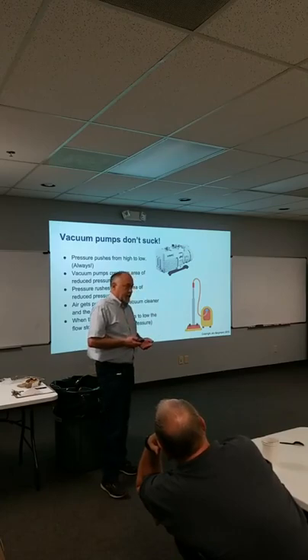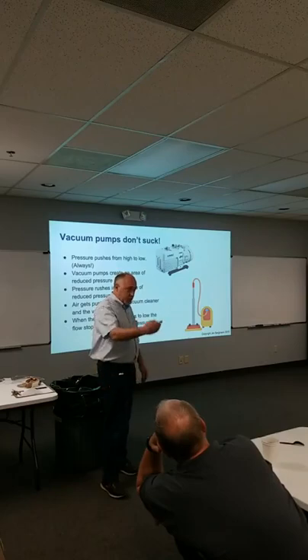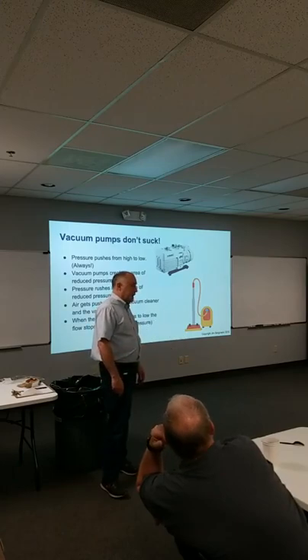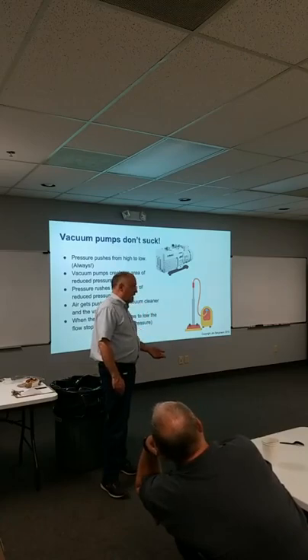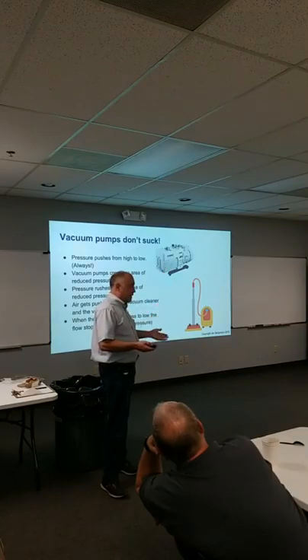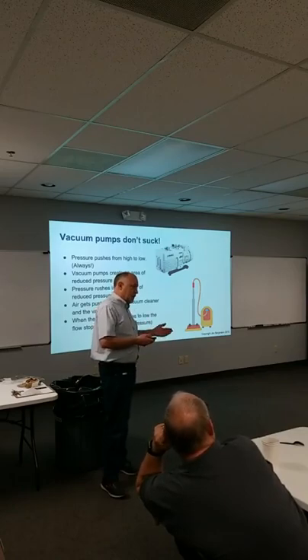When you look at an air conditioner, you're seeing the condensers getting bigger and bigger, and the condensing pressure dropping further and further. Back when we were in school, condensing temp over ambient was 30 degrees higher. You'd take your outdoor air and add 30 for the approximate condensing temp. Then came the 10 to 12 SEER, that dropped down to 25. Then came 13 SEER and it dropped down to 20. Right now we're at 17 plus SEER, and it can be as low as 10. You go, man, once you get it down to 0 it'll be perfect. Condensers will be huge, but if it's 0, heat transfer stops, right? We got to have a temperature difference for heat to transfer. We got to have a pressure difference for pressure to move.